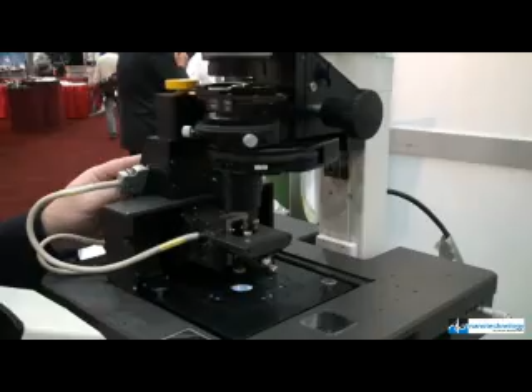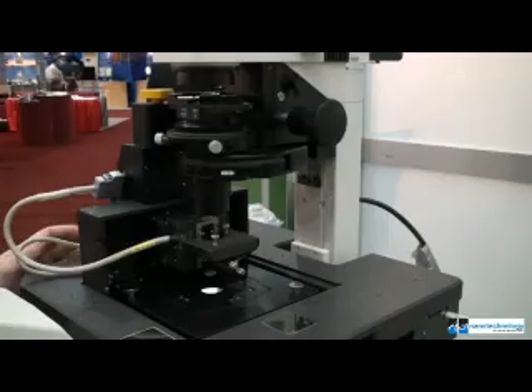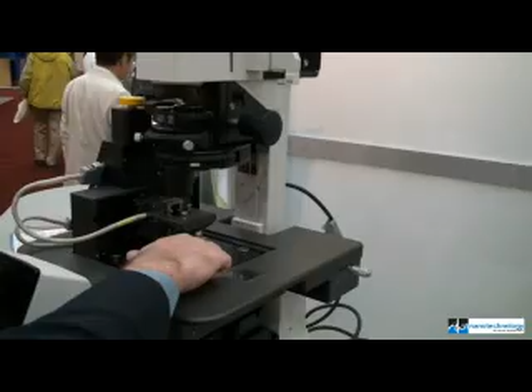And the AFM stage is also designed to be very user-friendly and functional for scanning in liquid. So we have a variety of liquid cells that allow the user to do experiments in liquid, look at live cells. And like all of our other XE products, this system is designed with a completely decoupled XY scanner from Z scanner. So the sample will be mounted on the XY stage and scanned, rastered in the XY direction.